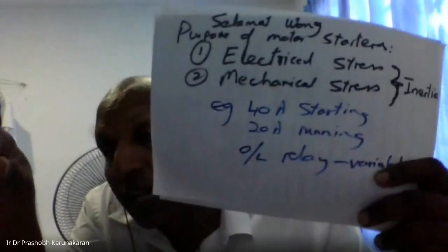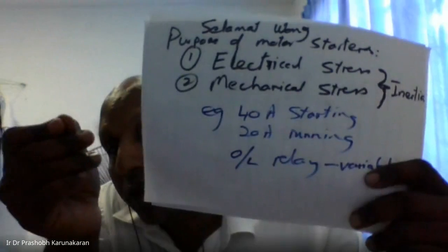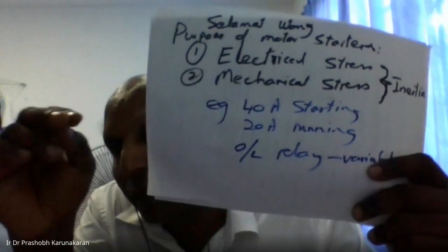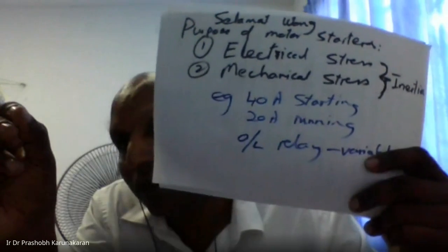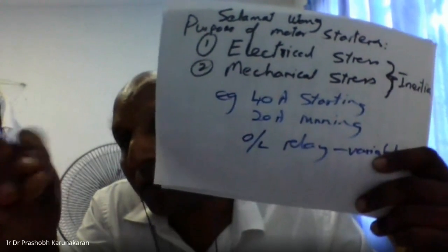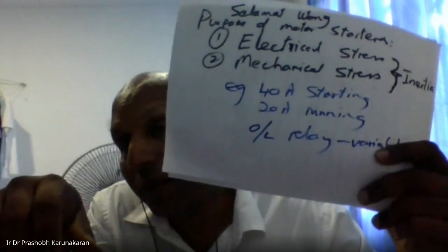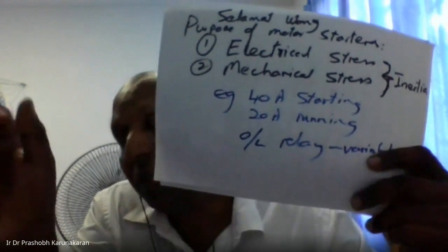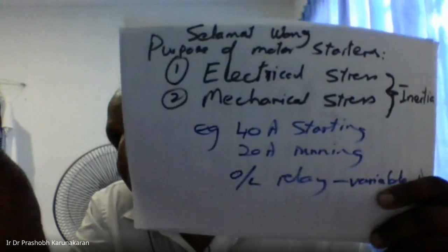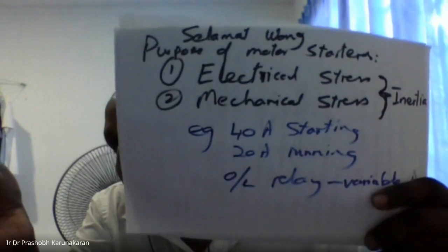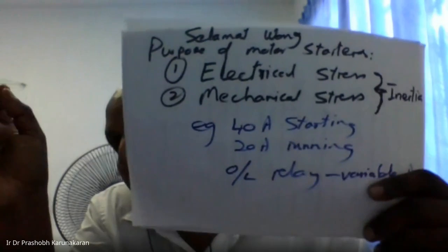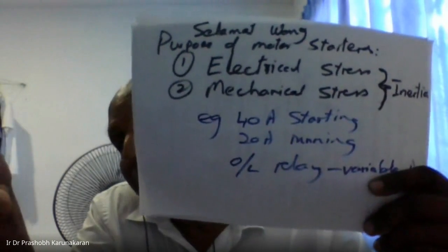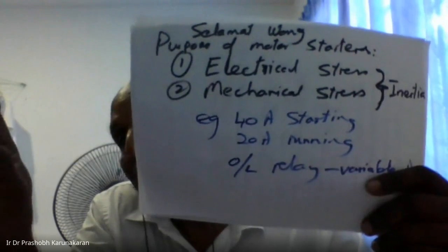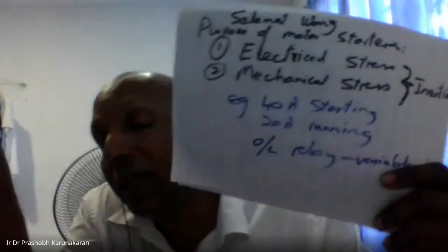So the overload relay has a variable amp. Why? Because starting is 40 amp, right? So when you want to start, you put the relay at 43, a bit higher than what it is using, so you can start. After it has started, you put it down, because starting is only 6 seconds and the human is still there. Running is 20, so you put 23 or something like that. So 43 to enable it to start, and after starting, you put it down to 23. If you keep it at 23 all the time, what happens? You cannot start, because starting you take 40. So that's why this overload relay has a variable current.